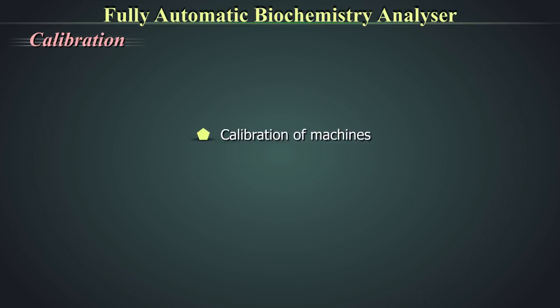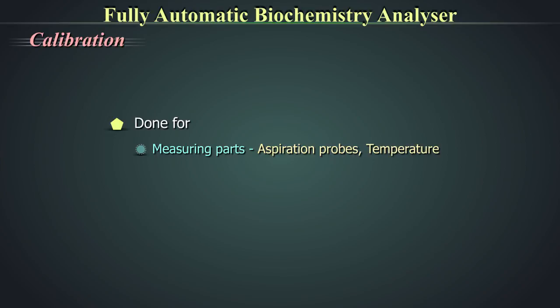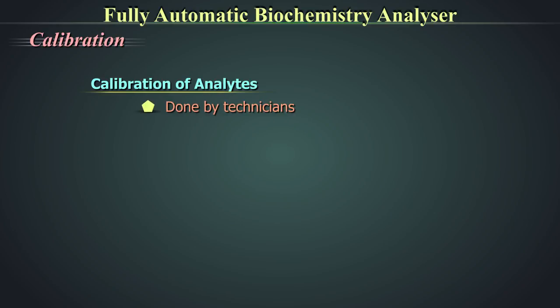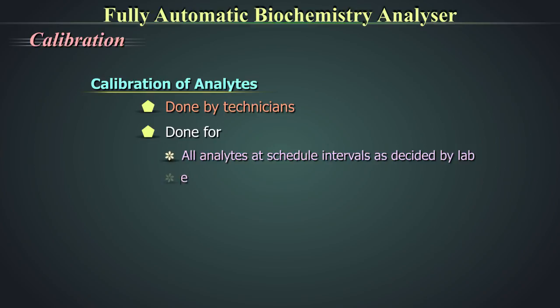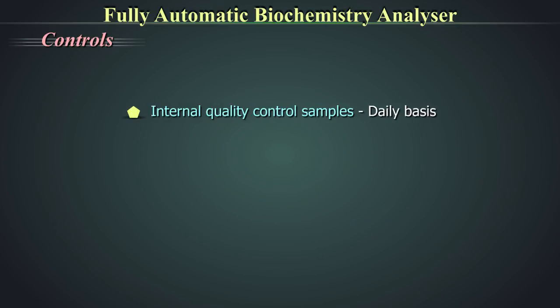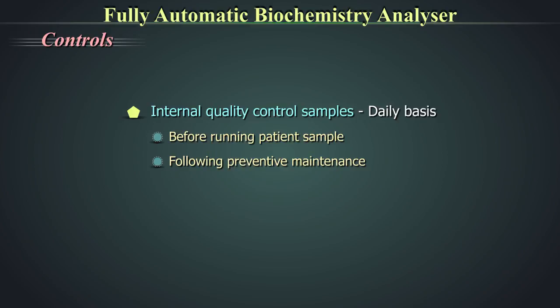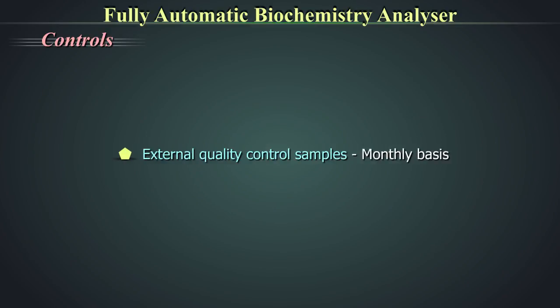Calibration of the machine is done by company engineers for measurable parts like aspiration probes, temperature, and optical parts like photodetectors and light source at regular intervals. Calibration of analytes is done by technicians for all analytes at scheduled intervals, during lot change, and post-maintenance or repair. Internal quality control samples are run on a daily basis before patient samples and following preventive maintenance or repair. External quality control samples are run usually on a monthly basis.